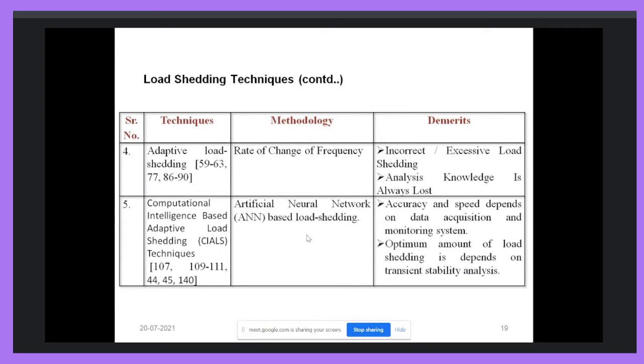Our focus is on artificial neural network based load shedding. It is accurate, and its speed depends on the data acquisition and monitoring system. Once the artificial neural network is trained and tested, its speed depends only on how fast we give input to the neural network, because there is no appreciable processing time. It is very fast. Its accuracy depends on the data acquisition system, and the optimum amount of load shedding depends on transient stability analysis.